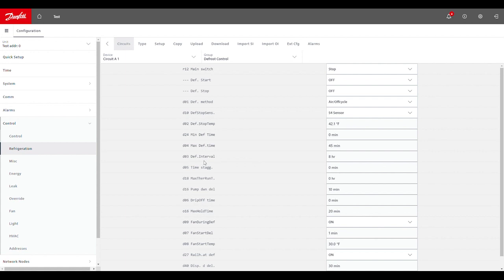So here we're looking at parameter D03 we want to pay attention to before we actually set the schedule itself. This is a fail safe setting so that if the scheduled defrost that we'll set up next aren't able to be broadcast from the system manager down to the case controller, that this parameter acts as a fail safe to still allow the case controller to go into a defrost. So what we want to do here is set this to one hour past our normal interval. So for example, if we're defrosting four times per day or once every six hours, we would want to set this fail safe parameter to seven so that it's one hour past that normal interval.